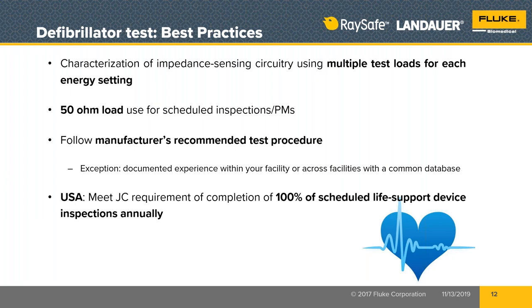And then I also want to know how much output energy was dialed in. If it's an AED, it's going to be whatever the AED is set to deliver. And sometimes there are three different energy levels and it escalates through. But on the ACLS defibrillators, where the doctor or the nurse is dialing the energy value, we would like to know what was the energy value that you think was not delivered. And we will also bracket that if we can. So we'll test energies above and below and at that value, whatever it was. The data of the measurements that we collect in our testing will be what we use. We may plot that out as a graph so visually it's easy to understand for the doctor or the nurse. And we'll be able to have a different conversation with them.